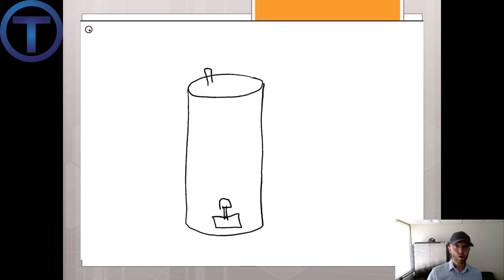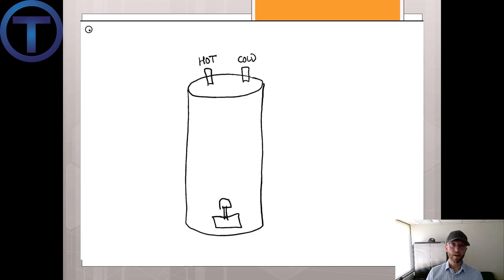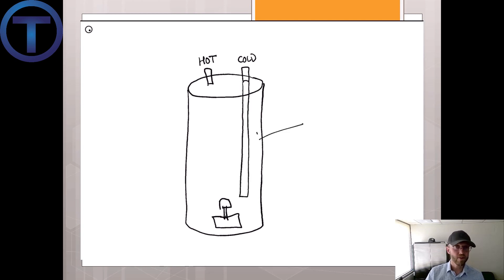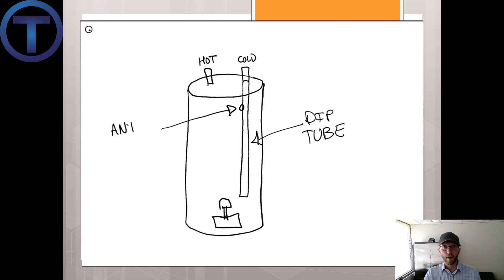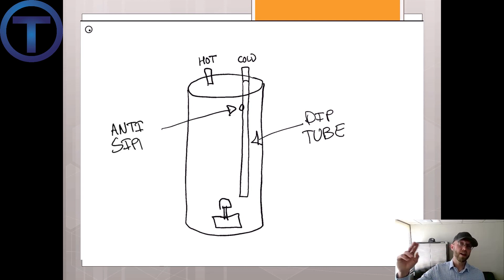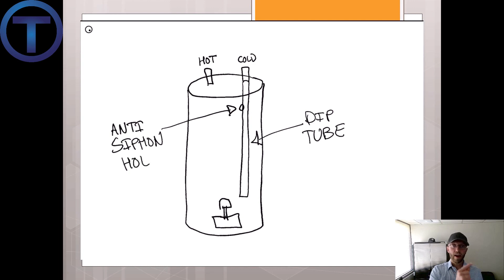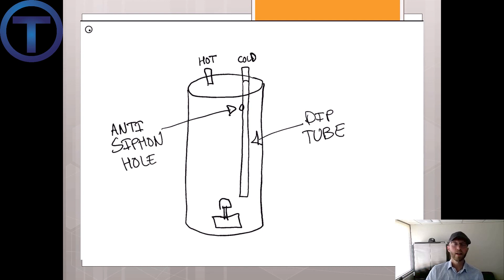In that dip tube, there is going to be a small hole towards the top. If there is a siphon created — a reverse pressure starting to pull water out of that water heater — that hole is going to allow air to come into the tank and break the siphon before it drains out the entire tank of hot water.